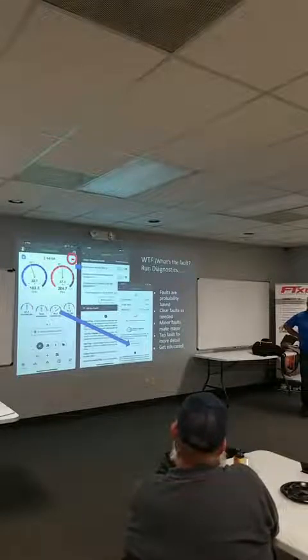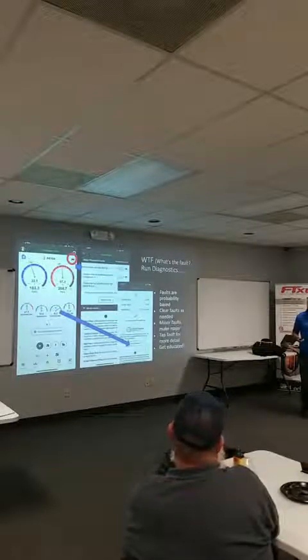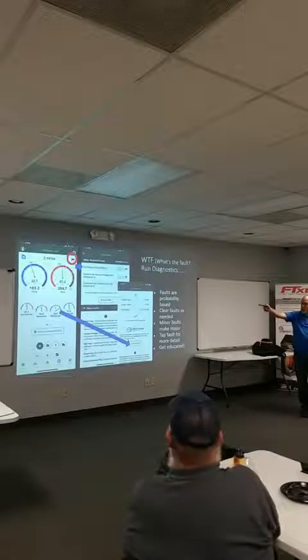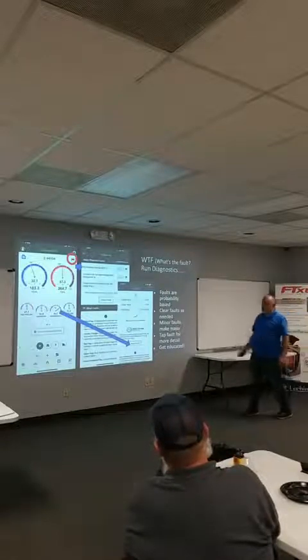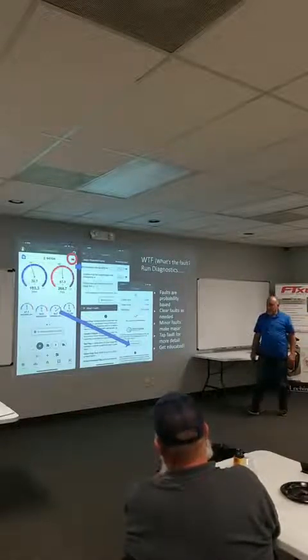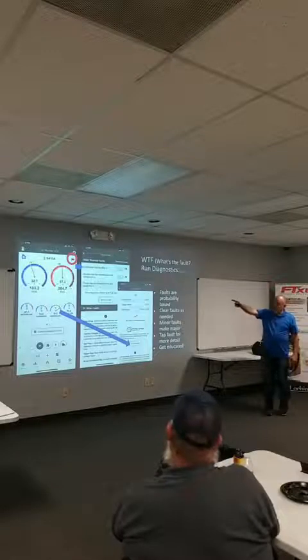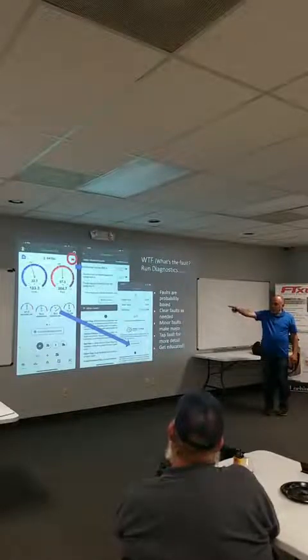So it could be like low suction pressure, high superheat, low head pressure, maybe a high approach, and then low capacity, or low delta T, right? So everything that we measure, with the exception of very few things, has a target in Measurequick. So we're actually calculating what your suction pressure should be, your head pressure should be, what your suction line, your superheat, your subcooling will be.